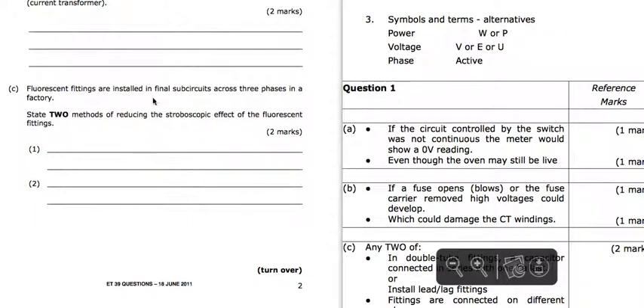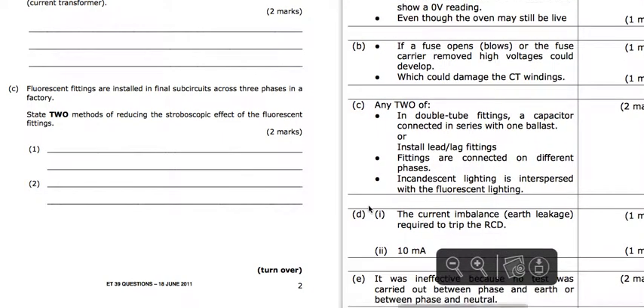Fluorescent fittings installed in final subcircuits across 3 phases in a factory. 2 methods of reducing the stroboscopic effect. So the stroboscopic effect, if they flash at the same rate as the machinery is turning, it may make the machinery look as if it's stationary. Someone could put their hand in there. So how do we make sure that doesn't happen?